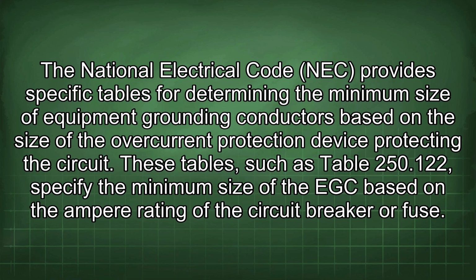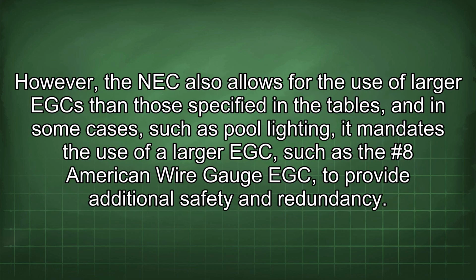The National Electrical Code (NEC) provides specific tables for determining the minimum size of equipment grounding conductors based on the size of the overcurrent protection device protecting the circuits. These tables, such as Table 250.122, specify the minimum size of the EGC based on the ampere rating of the circuit breaker or fuse. However, the NEC also allows for the use of larger EGC than those specified in the tables, and in some cases, such as pool lighting, it mandates the use of a larger EGC, such as the #8 American wire gauge EGC, to provide additional safety and redundancy.